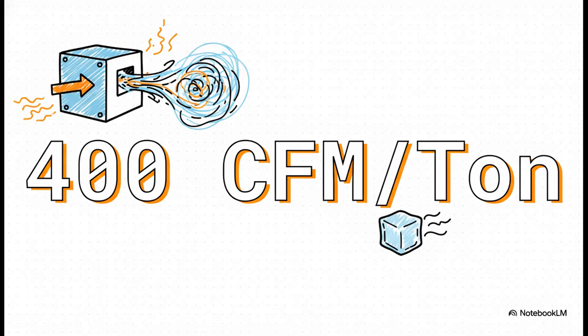Now, here's a classic rule of thumb that every single HVAC student and engineer needs to have in their back pocket. For standard comfort cooling, you're looking at about 400 CFM of airflow per ton of cooling. And remember, 1 ton of cooling is just a shorthand for 12,000 BTUs per hour. This is an incredibly useful shortcut for quick, back-of-the-napkin calculations early on in a project.